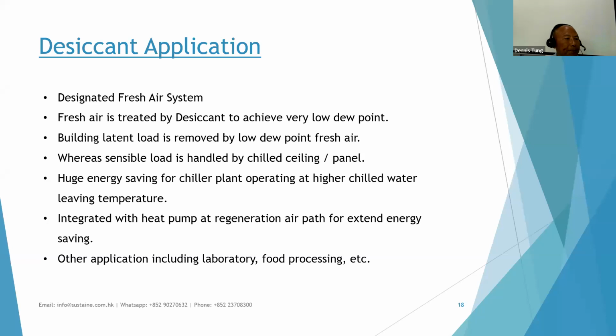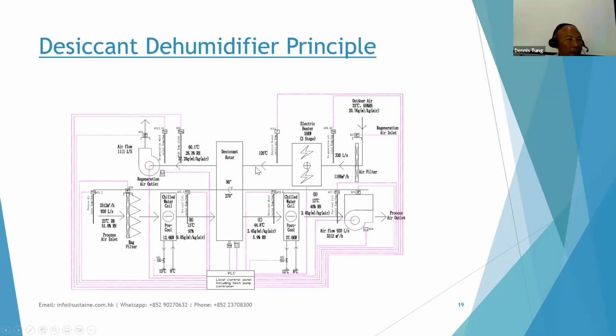So therefore, an integrated heat pump in the regeneration path can achieve extended energy saving, and this is very useful in laboratories and food processing. So I would like to explain the preliminary principles of this desiccant operation. It's actually very simple. Our fresh air comes in and goes through a pre-cool coil, which brings it down to 13 degrees Celsius, and then it goes through the desiccant wheel, which absorbs the moisture, and the air leaving the desiccant wheel will go up a little bit in temperature. If we want to bring it down, we can put a post-cool cooling coil after it, so that we can achieve a very low dew point supply air.